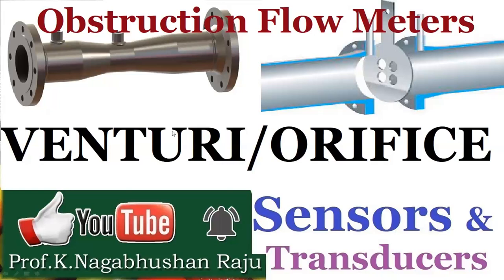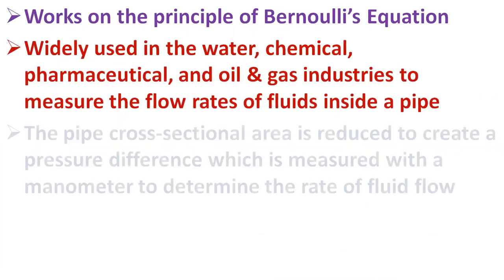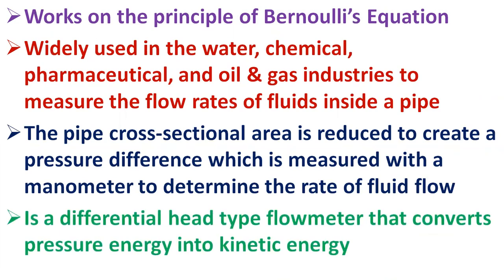A venturimeter is a type of flow meter that works on the principle of Bernoulli's equation. The device is widely used in water, chemical, pharmaceutical, oil and gas industries to measure the flow rates of fluids inside a pipe. The pipe cross-sectional area is reduced to create a pressure difference, which is measured with a manometer to determine the rate of fluid flow. So the venturimeter is a differential head type of flow meter that converts pressure energy into kinetic energy.